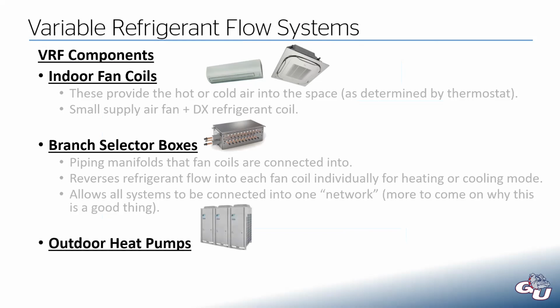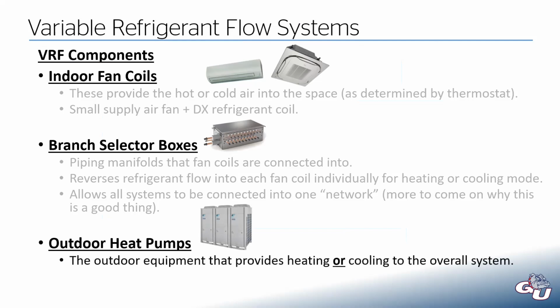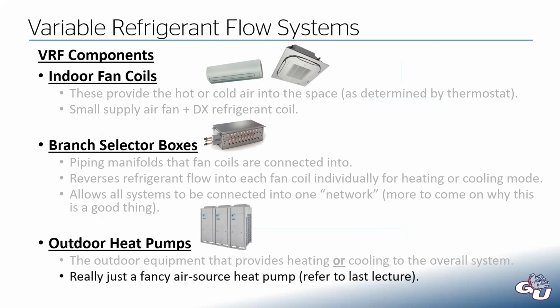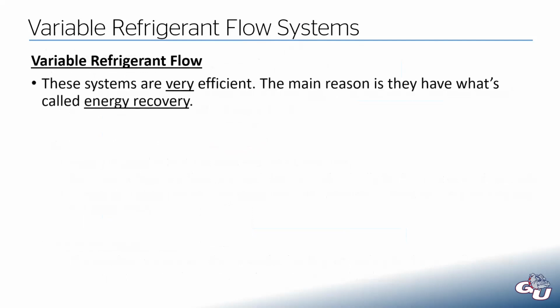And then we have the outdoor heat pumps. So this is the thing that's really going to provide our heating or cooling to the overall system. And it is a special type of heat pump, but fundamentally, it's operating on the exact same principles. It's either going to pull heat out of the air to deliver into our VRF system, or it's going to reject heat into the air from the VRF system, depending on what's going on. Are we in heating mode? Are we in cooling mode? These systems are extremely efficient. Main reason being is they have what's called energy recovery.